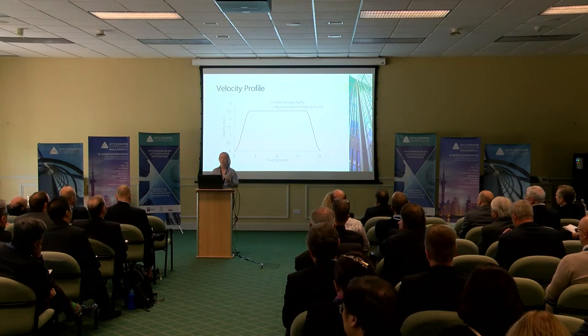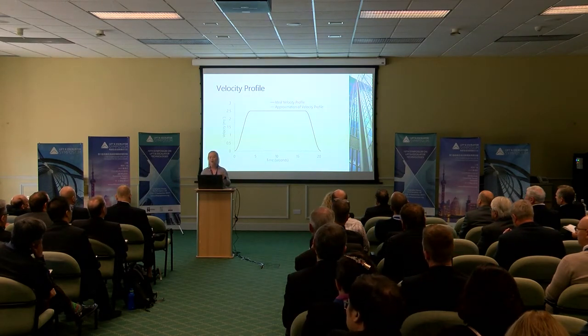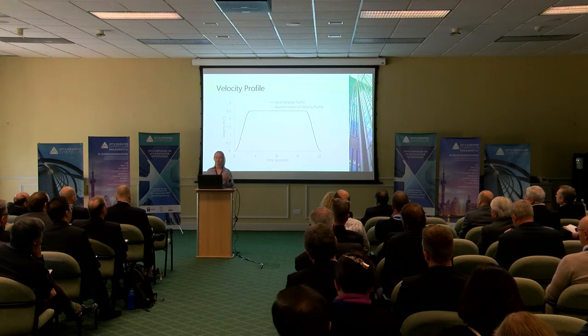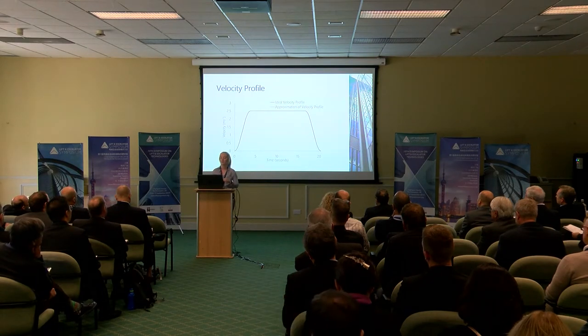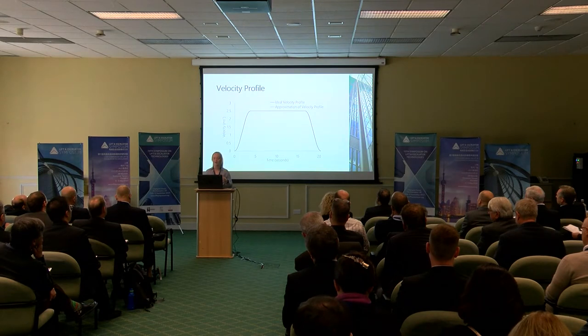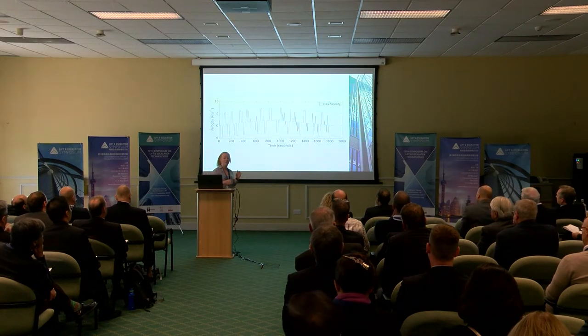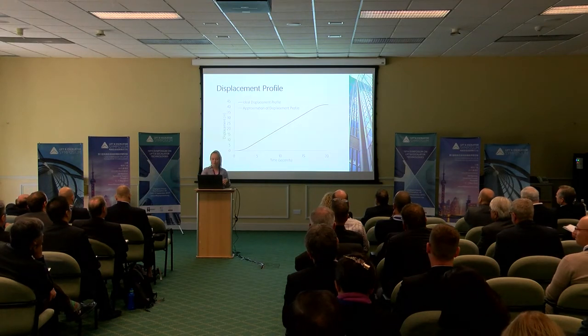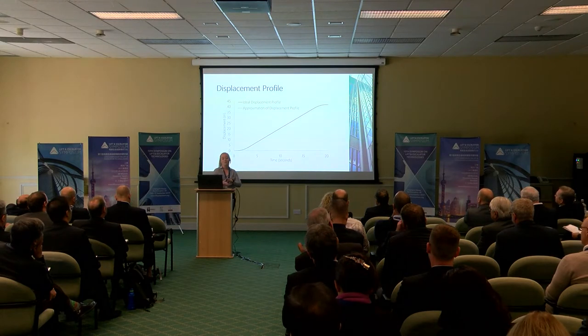Slightly more work goes into creating the velocity profile. From ideal lift kinematics, it's known that the integral of a single lift trip acceleration profile should equal zero, since the lift starts and ends stationary. To tackle anticipated accelerometer drift, should the integral of a single lift trip not equal zero, a scaling factor is applied based on the difference between the integrals of the acceleration and deceleration phases, such that the integral equals zero. This shows what happens over multiple trips when a scaling factor is not applied — you can see the velocity profile drifting when it should stay constant. Finally, by integrating the adjusted velocity profile, you achieve the displacement profile, which again matches the ideal.